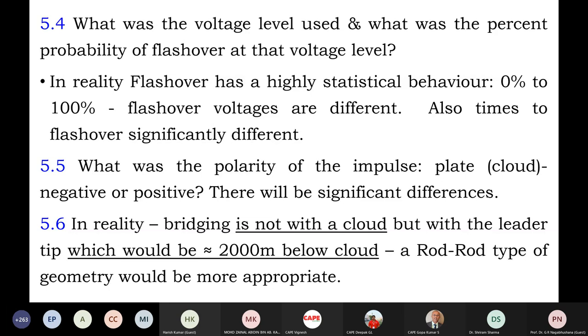Now, next, what was the voltage level used in these experiments? What was the percent probability of flashover at that voltage level? I'm sure every high voltage engineer knows that the flashover probability of a gap depends upon the voltage. For example, at a certain voltage, there may be no flashovers even if we apply 10 impulses. These are typical numbers that we use in laboratories. If I go on increasing, at some level, out of the 10 impulses, only one or two may flash over. They call that 10% flashover probability. Like this, we can go to the 50% probability level, which we call the critical flashover level.